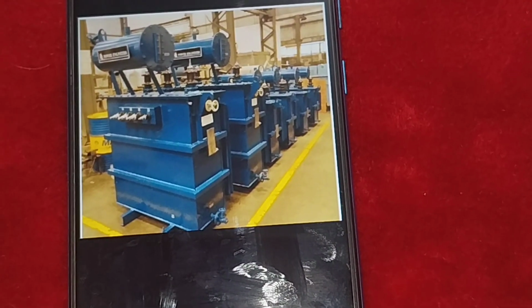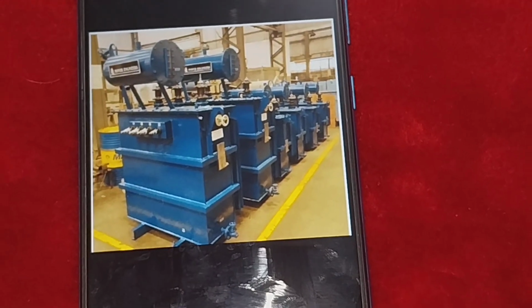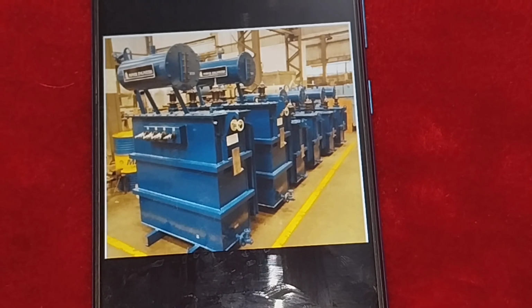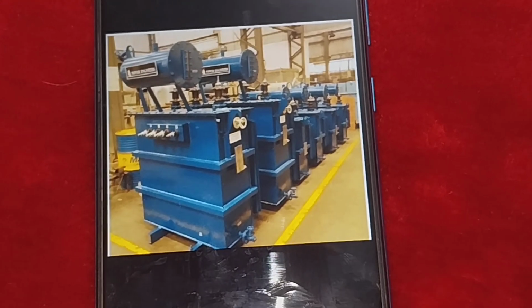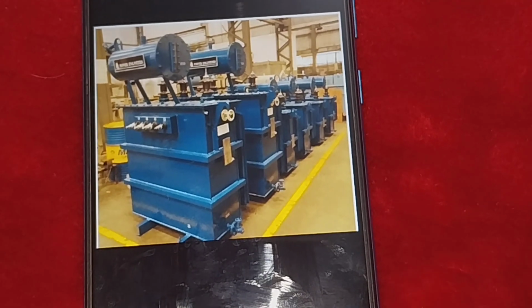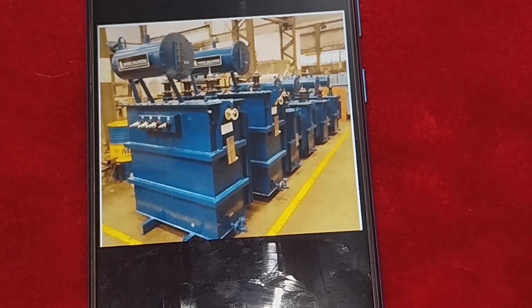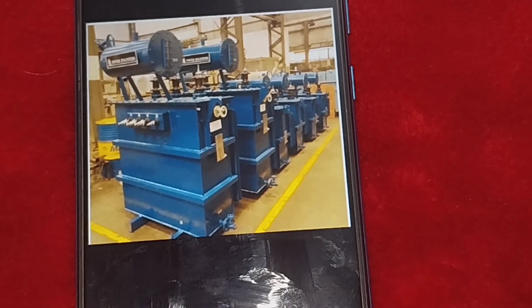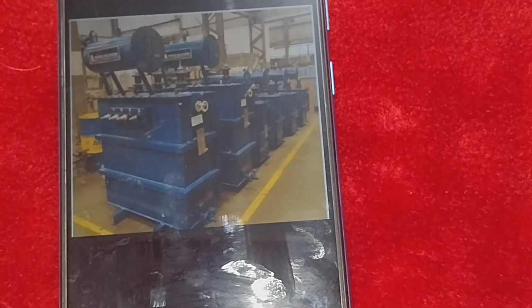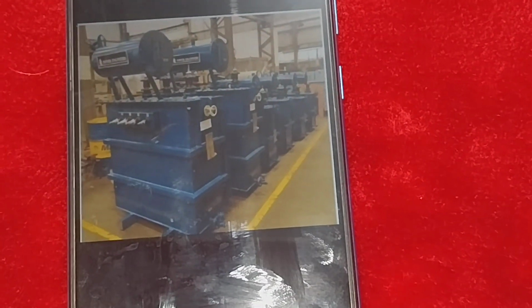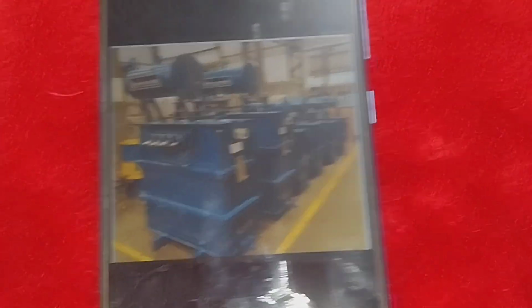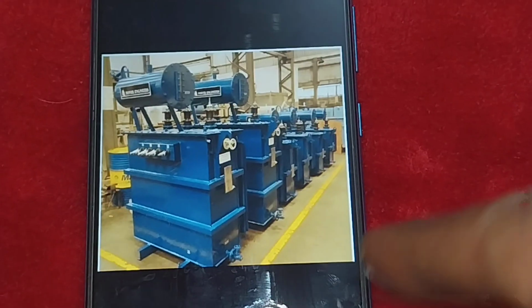Then there is DVDF, or double voltage double frequency test. This test is done to ensure the quality of interturns of the winding, that is, the insulation between successive turns of the winding.